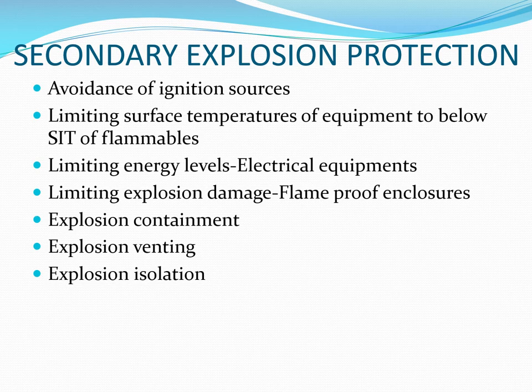Secondary explosion protection is used when releases cannot be eliminated completely, and inerting in working areas is not always possible. When primary protective measures alone are not sufficient, secondary measures are necessary for safe operation. These include avoiding ignition sources, limiting surface temperatures of equipment to below the self-ignition temperature (SIT) of flammables, limiting energy levels through intrinsic safety in electrical equipment, and limiting explosion damage through flameproof enclosures, explosion containment, explosion venting, and explosion isolation.